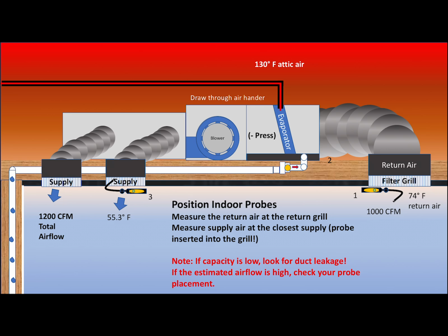And if they don't agree, if you're getting a lot of discrepancy, something's wrong, and it's usually your probe placement that's wrong. We have been to the National Institute of Standards and Technology and tested the airflow calculations against a sharp edge orifice, flow funnel, Wilson flow grid array, a bunch of different methods of measuring airflow, and we're consistently within 1 to 3%. So we know that calculation is very precise, but it's very dependent upon good probe position. And evaluation of any air conditioner is really dependent upon the probe position.